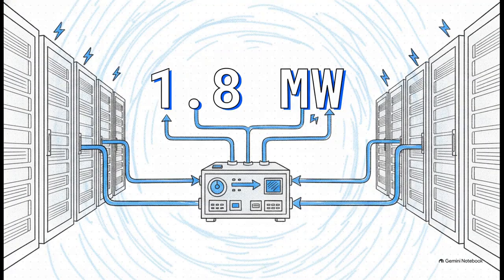Once you've mastered the single rack, you just multiply those foundational blocks. But as we zoom out from a single rack to an entire row of servers, the cooling requirements scale exponentially. Enter the in-row coolant distribution unit. This single unit steps up the game dramatically, supporting a staggering cooling capacity of up to 1.8 megawatts. It prevents any interruption to the cooling flow across an entire row of massive AI compute power.